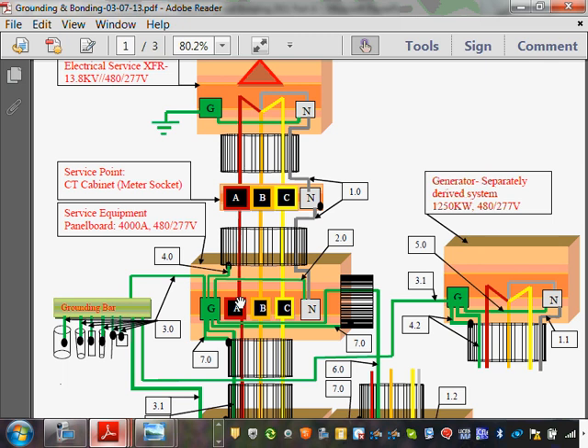There are two ways of doing it. Remember, there are 10 conduits coming in here. You either take one wire from each conduit to the ground, which is the best way to do it in this case, or you take one big fat one and go conduit 1 to 2 to 3 to 4 to 10 and to the ground. That's daisy chaining. Those are the two options. Daisy chaining is good if your system is small, because you end up with a smaller conductor. If your system is big, like 4,000, you might end up with 800 kcmil. How are you going to go from conduit 1 to 2 to 3 with all the lugs and tying them? It becomes too big of a wire to work with.